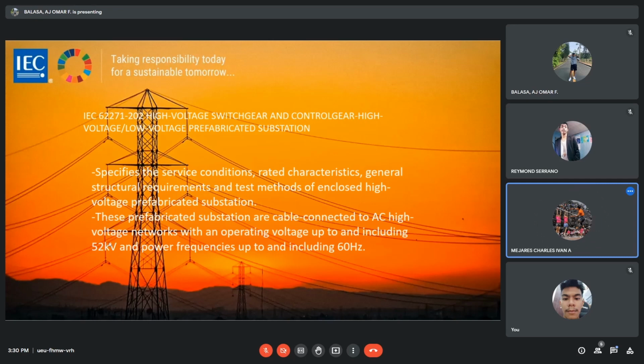A high voltage switchgear prefabricated substation comprises an enclosure containing, in general, the following electrical components: high voltage switchgear and control gear, auxiliary equipment and circuits. And the high and low voltage transformer prefabricated substation comprises an enclosure containing, in general, the following electrical components: power transformers, high and low voltage switchgear and control gear, high and low voltage interconnections, auxiliary equipment and circuits.